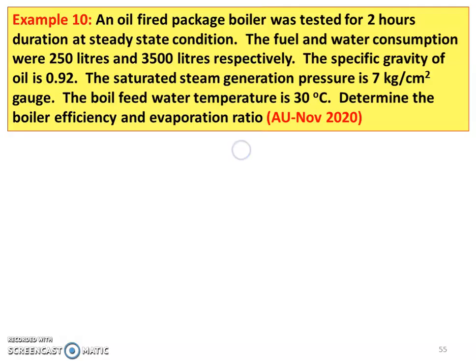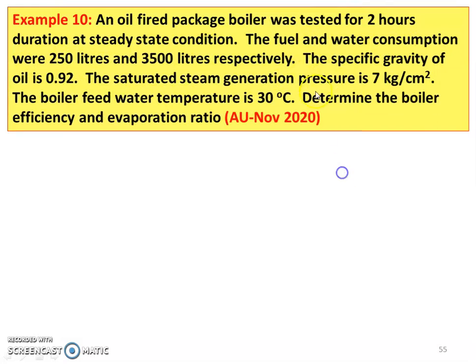We will take a few questions from the recent university question paper and solve the problems. Next example, from the November 2020 question paper: an oil-fired package boiler was tested for 2 hours duration at steady-state condition. The fuel and water consumption were 250 liters and 3500 liters respectively. The specific gravity of oil is 0.92. The saturated steam generation pressure is 7 kilograms per centimeter square. The boiler feed water temperature is 30 degrees Celsius. Determine the boiler efficiency and evaporation ratio.